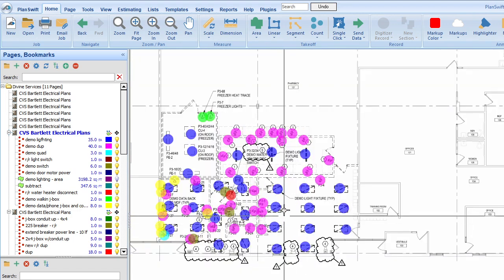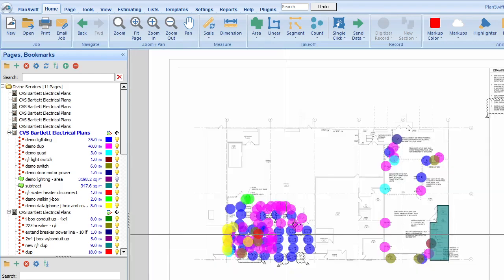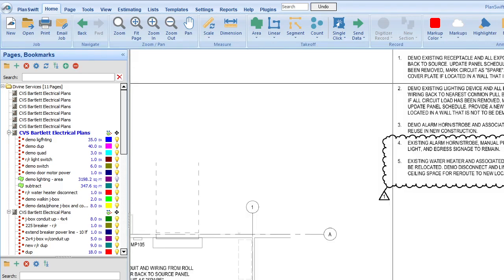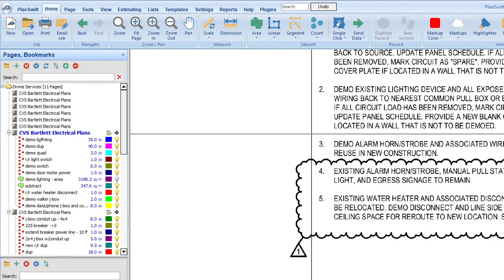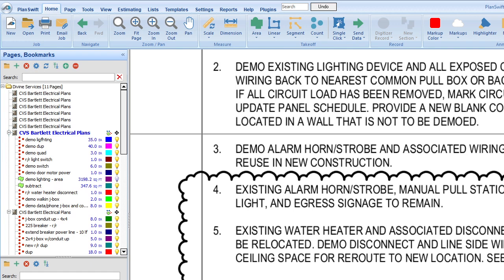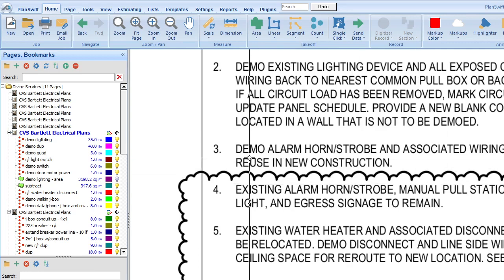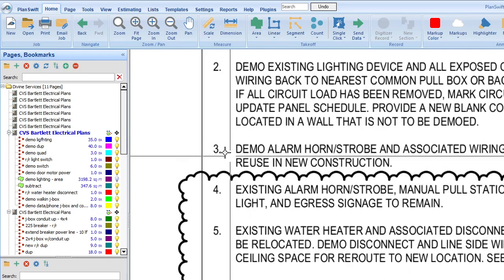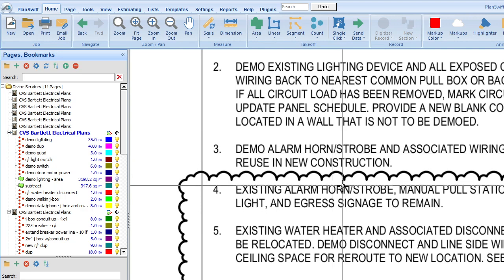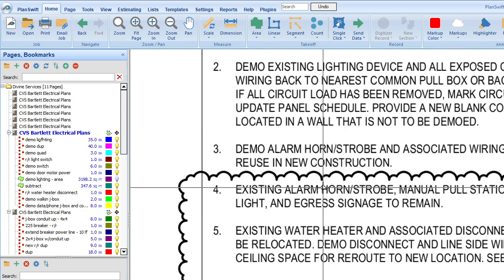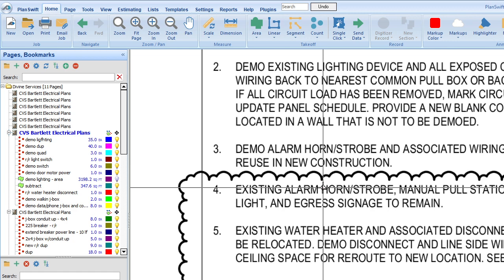So let's finish reading the notes. Number three, demo alarm horn strobe and associated wiring. Save for reuse. Okay, so when you are demoing for reuse, you're a little more careful with the demo, and so you're going to give it a little more time than you would for a regular demo. So a regular demo, you can rip it out, damage it in some way, and it's really not important because you're not reinstalling it. You can just cut it, whatever, cut the wires, whatever, but when you're going to reuse it, you're going to give yourself maybe double the time that you would. So like I said, I give most things an hour, and so in this case, because for the alarm...